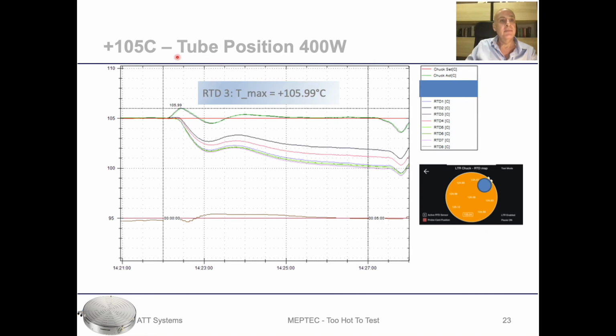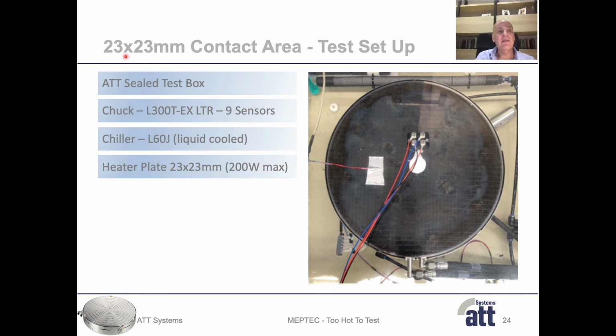The last test has been done at the tube position, and here exactly the same picture. RTD3 became the control sensor. The maximum temperature was around 106 degrees C, full heat dissipation, and then very stable temperature control around the set temperature. Okay, the last example is for our small devices, 23 by 23 millimeter contact area. We use the same test setup as before, the sealed test box, LTR chuck, 9 temperature sensors, L60J chiller. Of course, we used a different heater plate to reflect the smaller contact size.